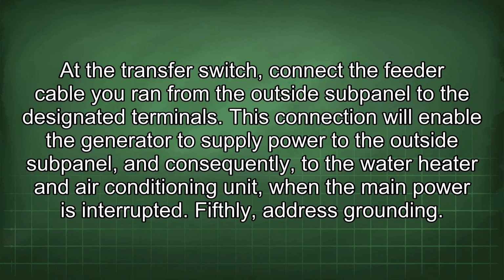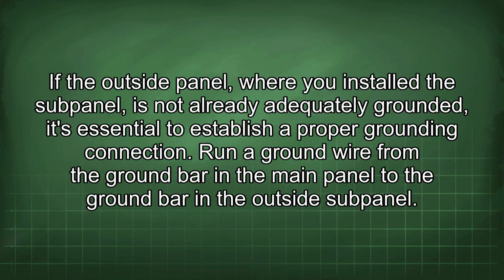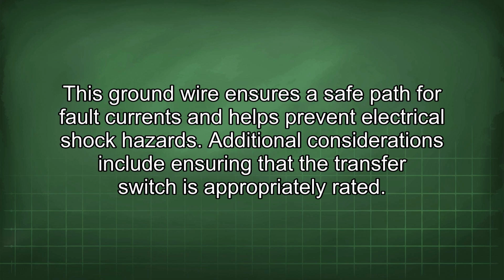Fifthly, address grounding. If the outside panel, where you installed the subpanel, is not already adequately grounded, it's essential to establish a proper grounding connection. Run a ground wire from the ground bar in the main panel to the ground bar in the outside subpanel. This ground wire ensures a safe path for fault currents and helps prevent electrical shock hazards.